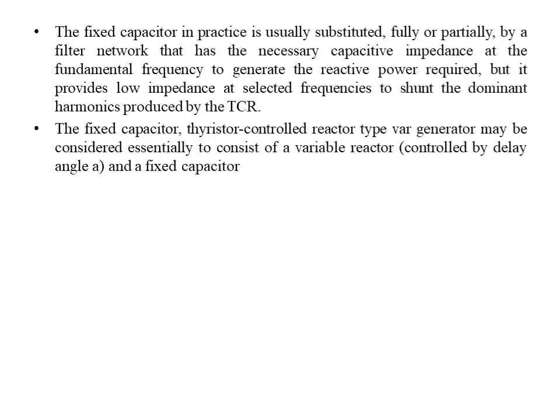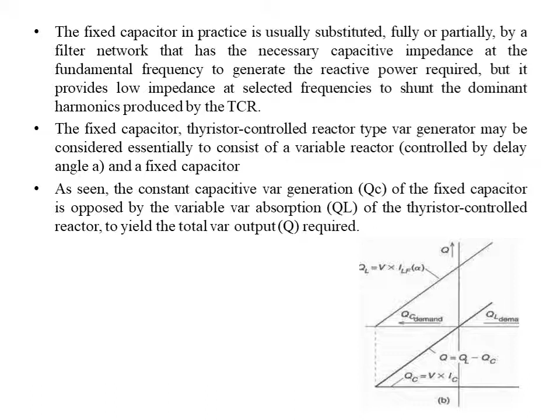So figure B shows the waveform of the demand of reactance of line, reactance of capacitors. So as seen, the constant VAR generation QC of the fixed capacitor is opposed by the variable VAR absorption QL of the thyristor controlled reactor to yield the total VAR output Q required. So the net VAR generation due to fixed capacitor and thyristor controlled reactor is given by Q is equal to QL minus QC, where QL is nothing but the reactive VAR absorption due to thyristor controlled reactor, and QC is the reactive power of the fixed capacitor. So the net reactive power is Q is equal to QL minus QC.